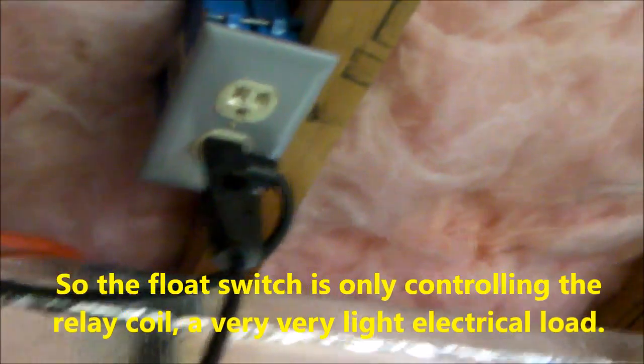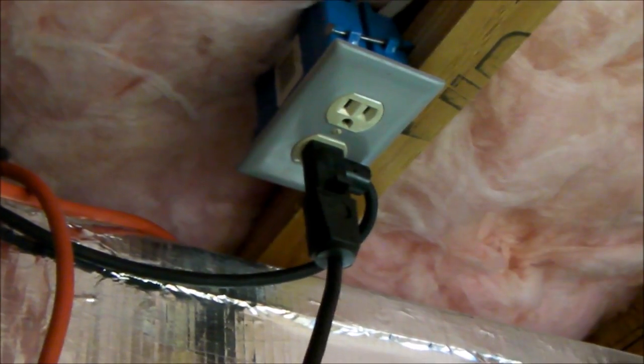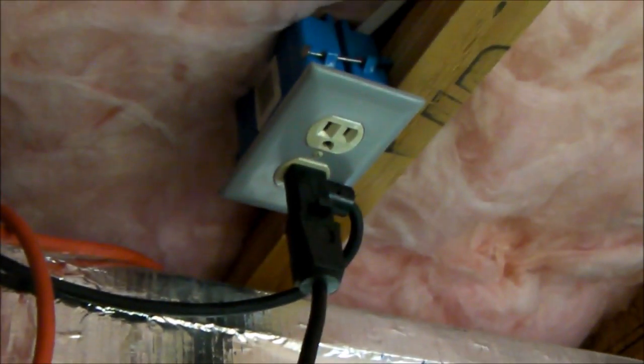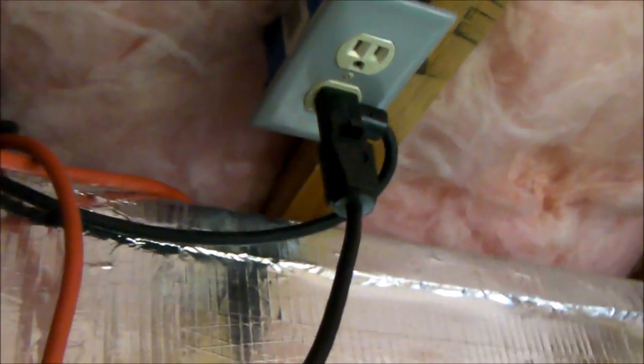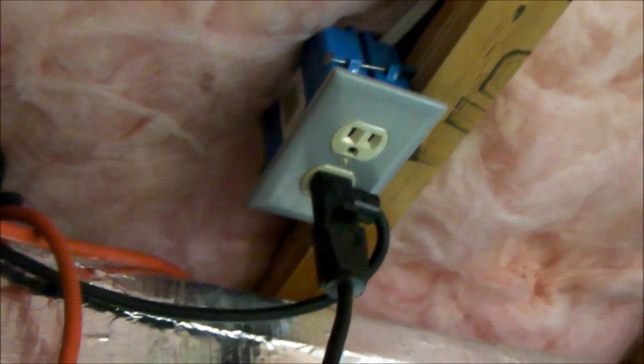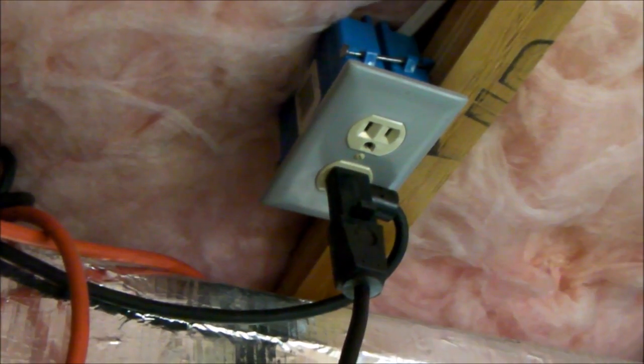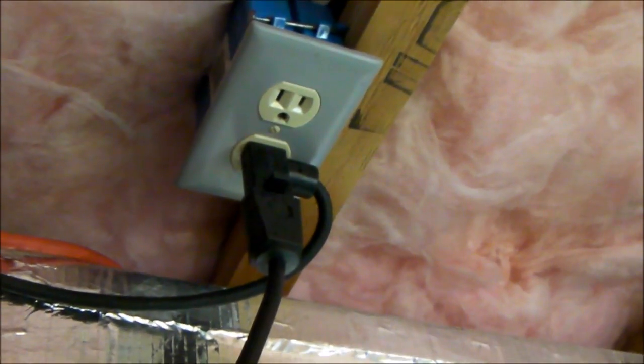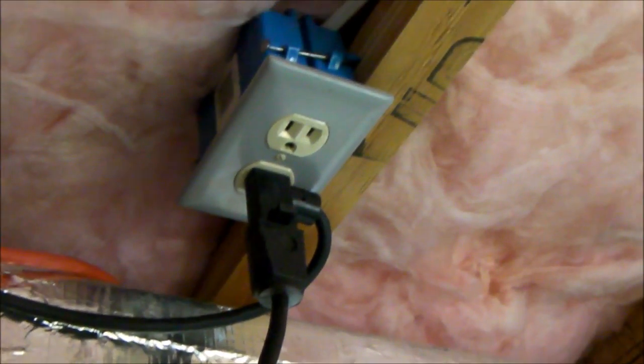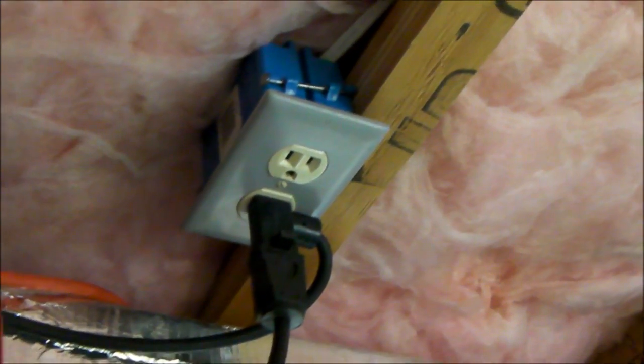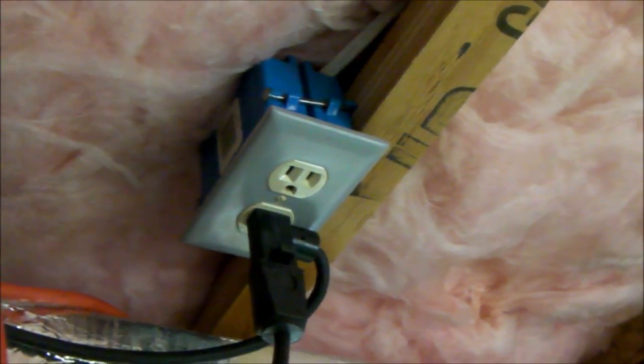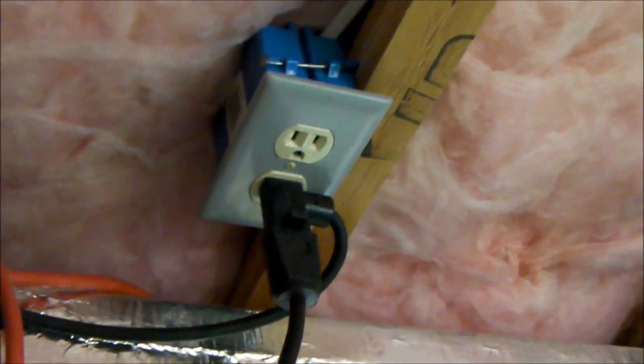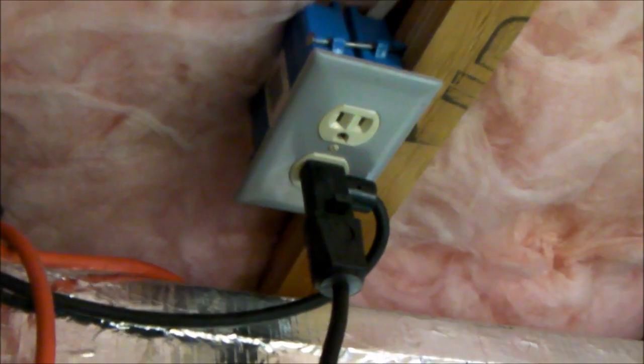And what's in the control box? Inside the control box is a power relay or a small motor contactor. In my case, those power relays, which are motor horsepower rated, that's really, really important. Make sure the relay you have purchased has a motor horsepower rating on it. Current rating in amps, in my opinion, is not quite as important as the motor horsepower rating. So make sure that the motor horsepower rating at 120 volts or 125 volts is suitable for the pump motor that's in your pit.